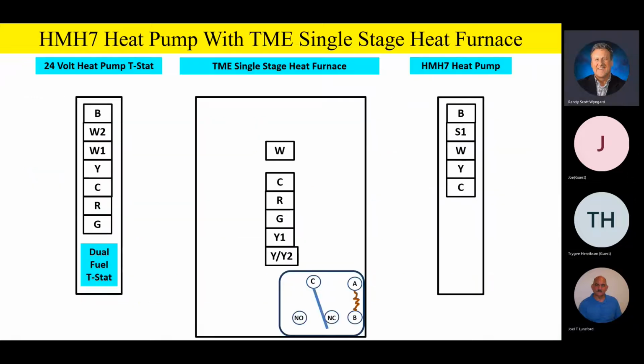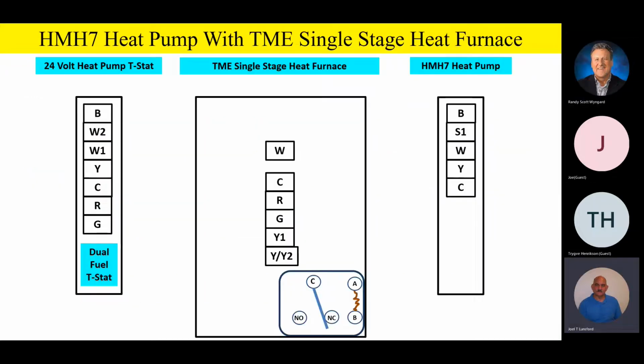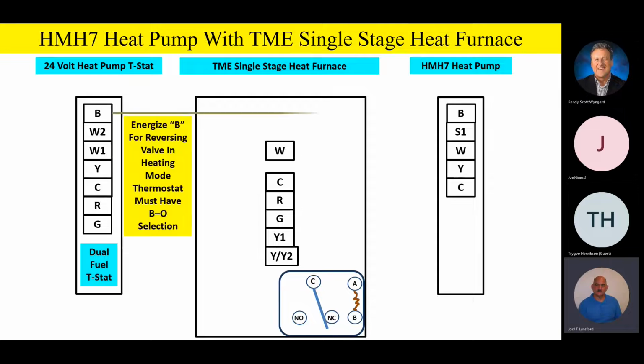Let's go ahead and start out with a TME single stage furnace. This does have hard screw terminals on it. So we're basically featuring terminals on the furnace and our outdoor unit. And remember that heat pump thermostat has to have dual fuel capability. So just like before, we're going to energize that B terminal for reversing valve operation in the heating mode. So we'll take B from the thermostat straight outside to the B terminal on the outdoor unit.